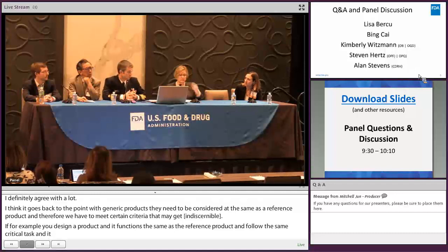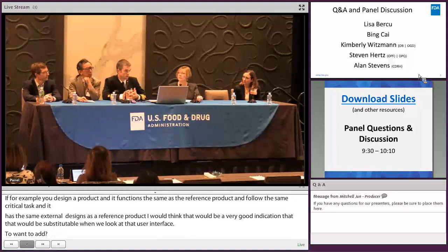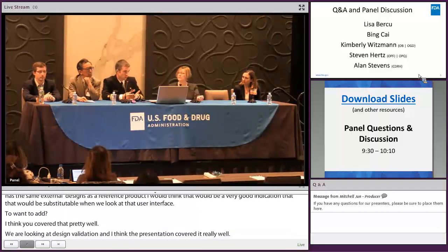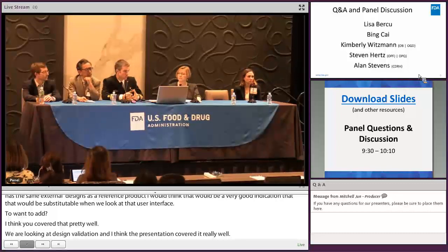Yeah, Kim, I think you covered it pretty well. The only thing I would say from a CDER standpoint, when we're looking at design validation of a device combination product, and I think the presentations covered it really well, is that what we're looking at in terms of substitutability is whether any of those differences are going to impact safety or effectiveness as it relates to substitutability. You may be able to do a standalone human factor study and validate the design of a device, but that's not the question being asked. We're looking at substitutability of that product. So that's the nuance. It's a different category of product when we're talking about combination products.